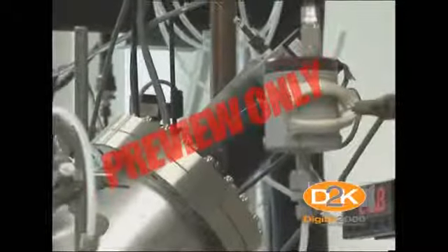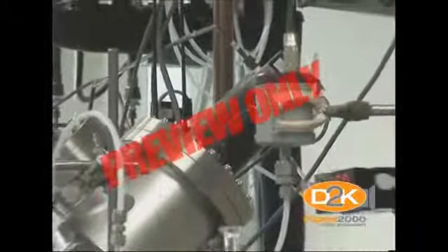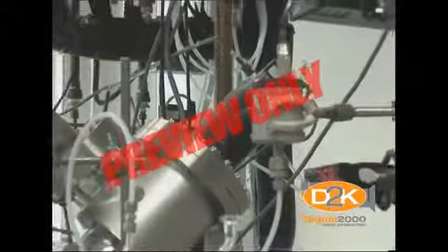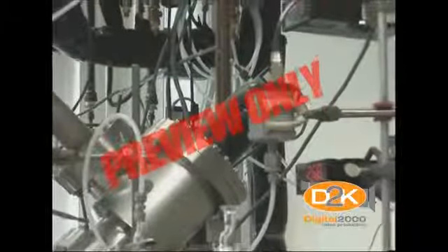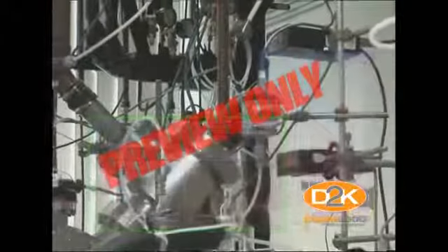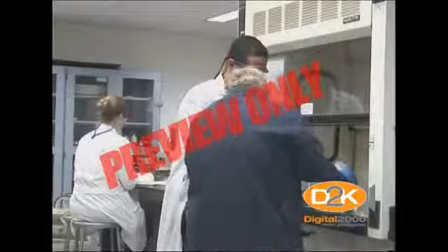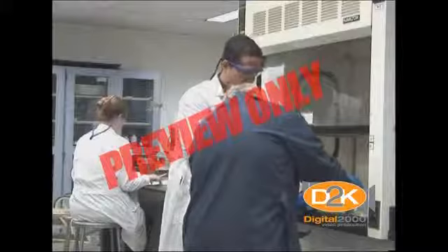Equipment and systems should be free of contaminating materials such as oil, grease, dirt, and chemicals, which may create a hazardous condition upon contact with the cryogenic fluids or gases. This is particularly important when working with liquid or gaseous oxygen. Mixtures of gases or fluids should be strictly controlled to prevent the formation of flammable or explosive mixtures.